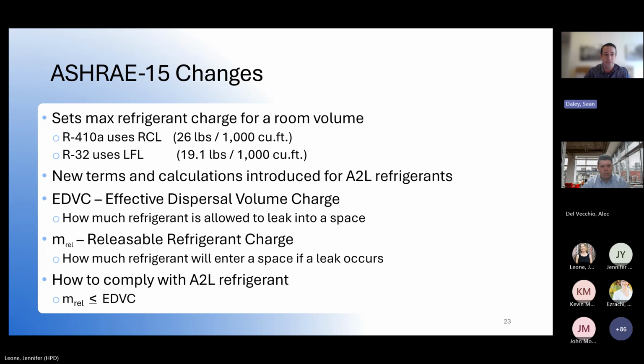So the new ASHRAE 15 2024 is the latest edition that has been published, and it gives us some new terms and calculations for the A2L refrigerants. The calculations have gotten a little more complex than what we're used to with R410A, just looking at charge amount and room volume. There are some other factors to consider now. One of the new terms is EDVC, effective dispersal volume charge, and essentially that is how much refrigerant is allowed to leak into a given space or room volume.